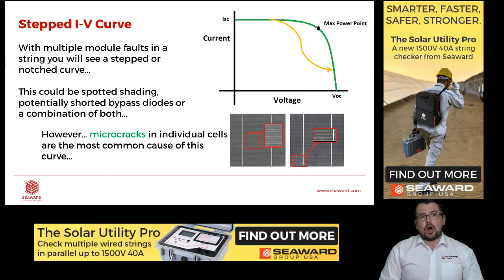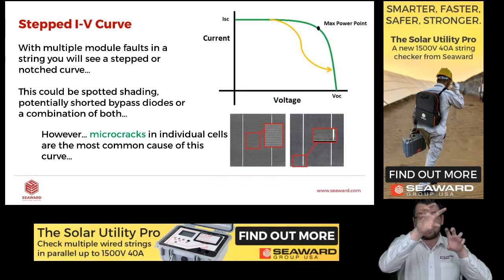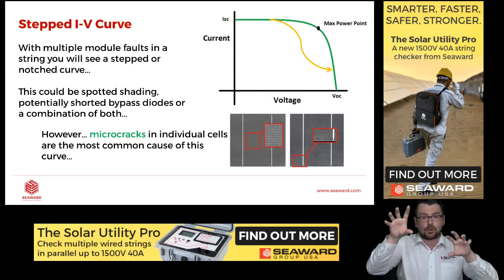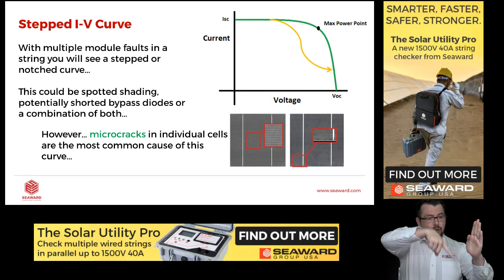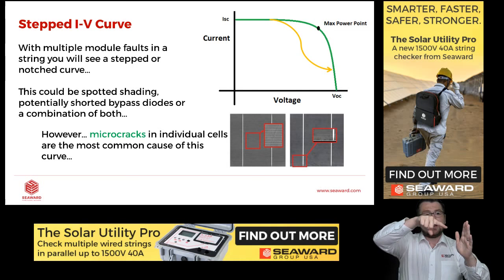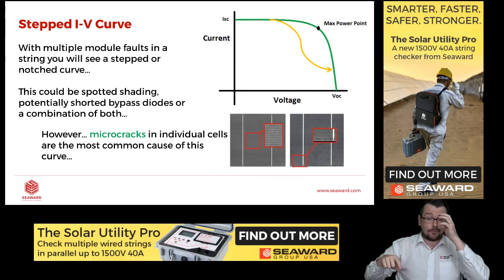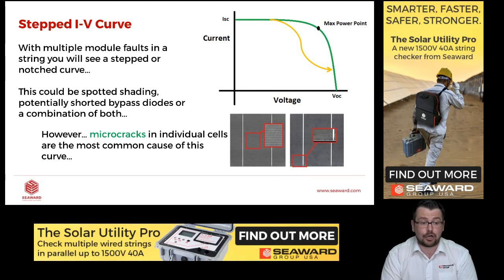This is one of the most common curves that I see in the field, and this is the stepped or the notched curve. So basically, when we have multiple faults in a PV string, we will see it going up and down like this. This could potentially mean we have spotted shading. So bird droppings or leaves on the panels, so the current is flowing, it's hitting the shade, and that's slowing it down and causing a notch in the short circuit current. However, the most common cause of this type of stepped curve is microcracks.